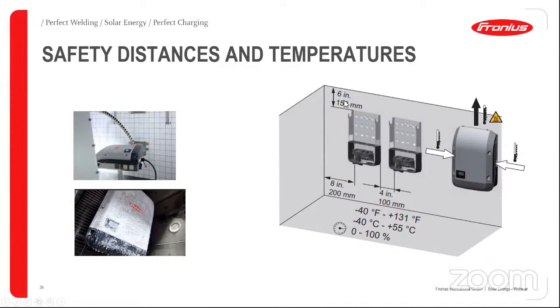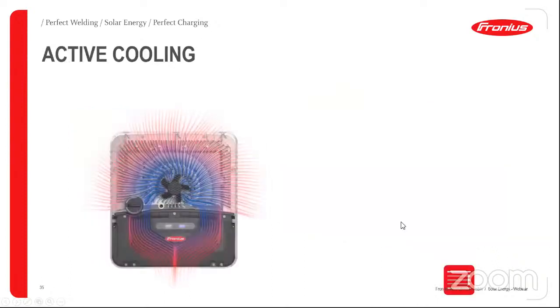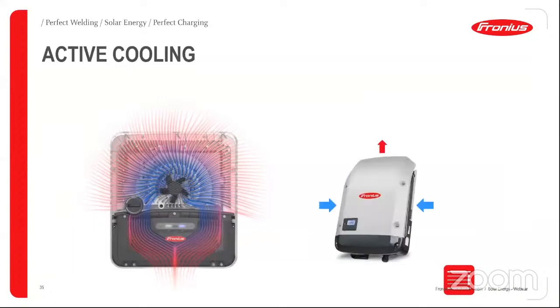And in the upper side, from where the high temperature is going out, we only need 15 centimeters. So it's very easy to find a place where we can put the inverters. And regarding ambient temperature, it's allowed to install the inverter up to 55 Celsius degrees. And this is allowed because we have a very nice cooling system. It is called active cooling. So it's our ventilation concept. It is the highest protection system for warm conditions like those in the Caribbean.